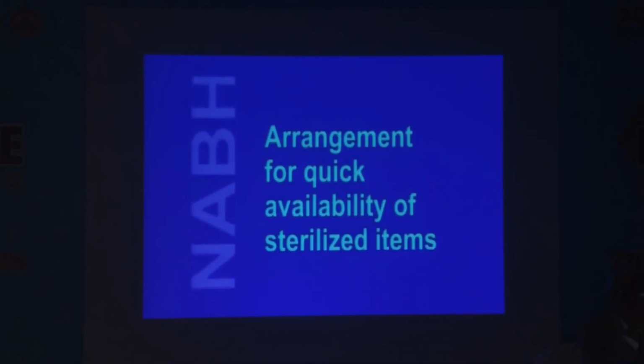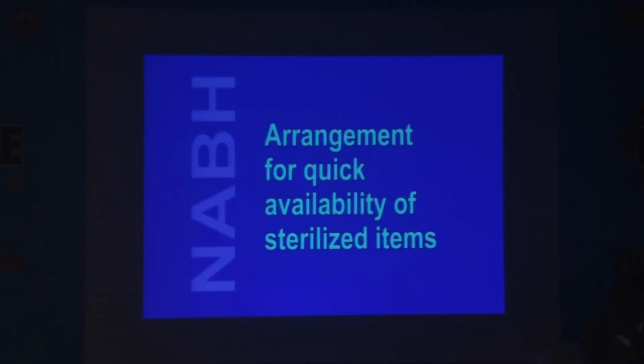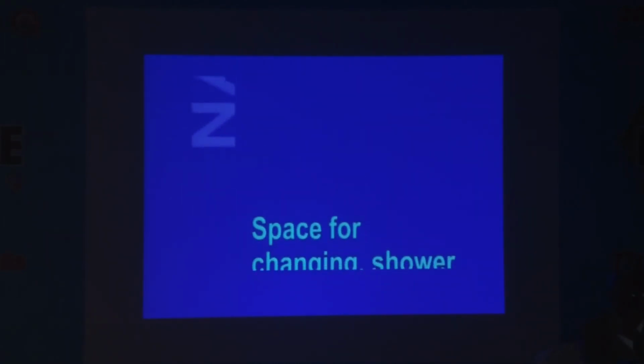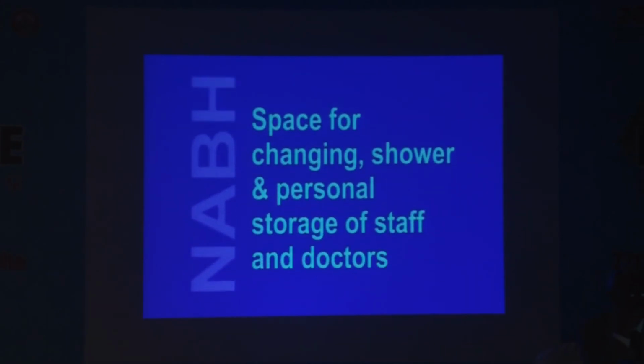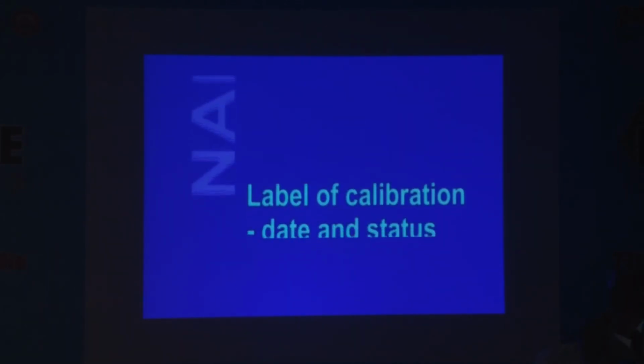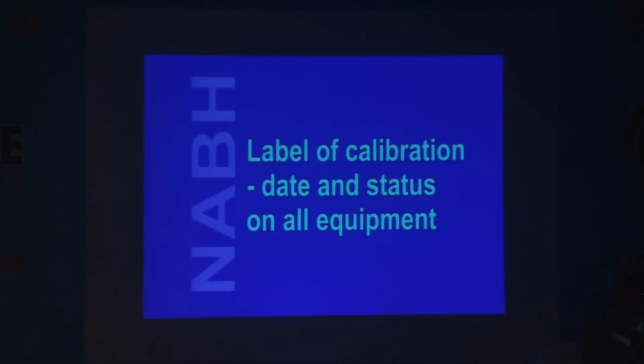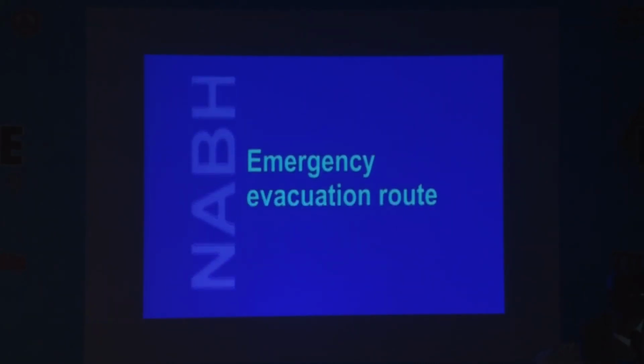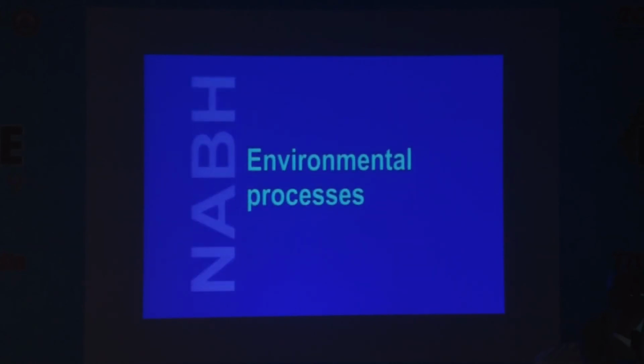Arrangement for quick availability of sterilized items, that is a flash autoclave or pre-autoclaved instruments, should be shown when they come for inspection. Space for changing and showering of staff and doctors, male and female, should be shown separately. Label of calibration, date and status of all equipment should be shown. That means you are doing your maintenance work for your phaco machine, so that label should be there. Emergency evacuation route should be shown. These are the things they insist.